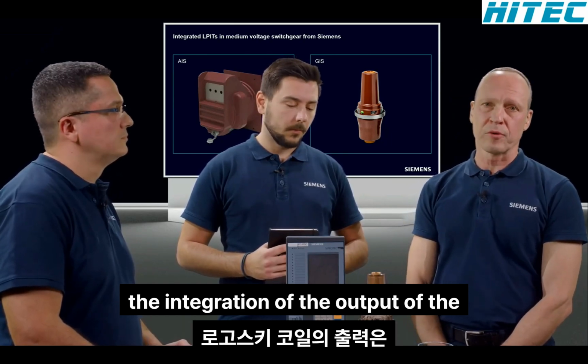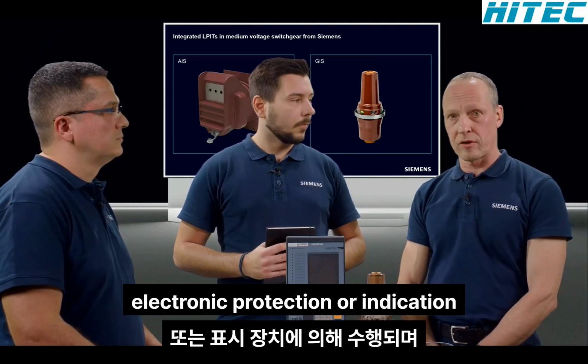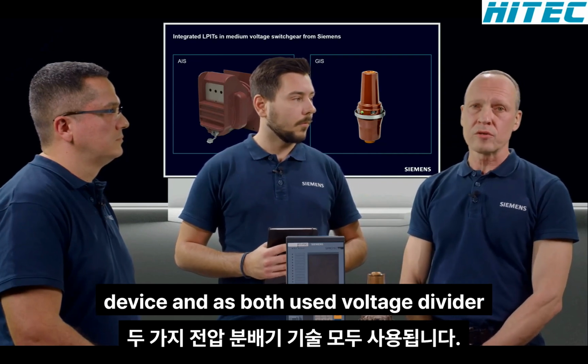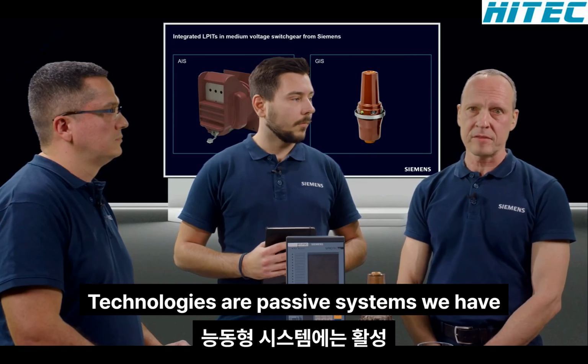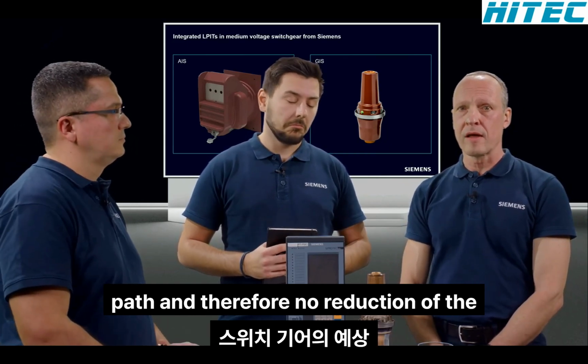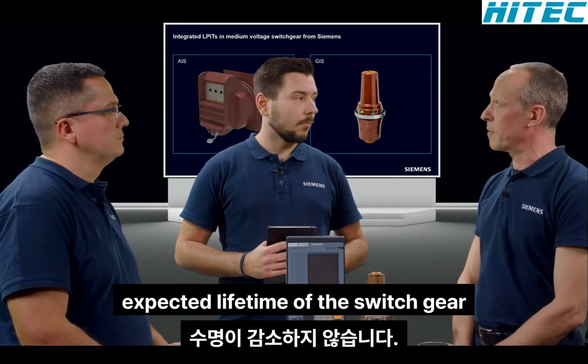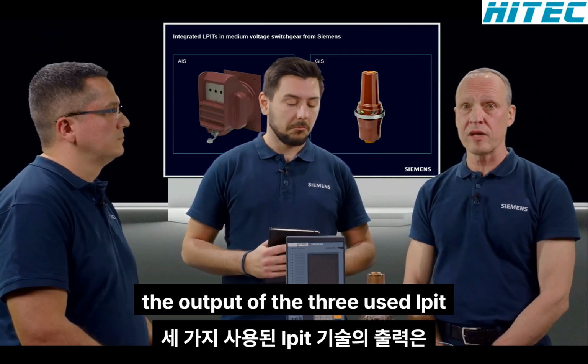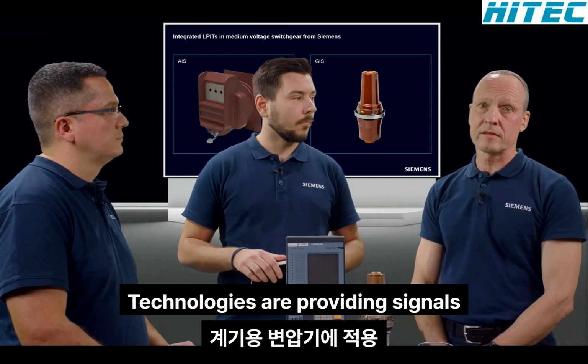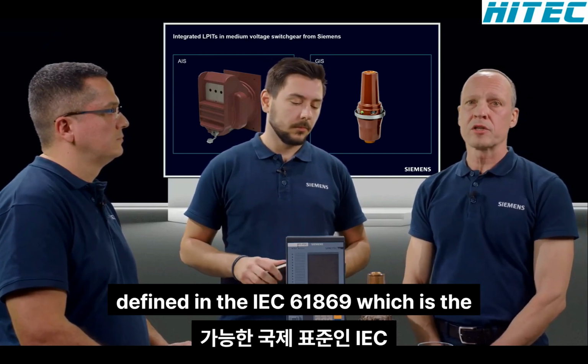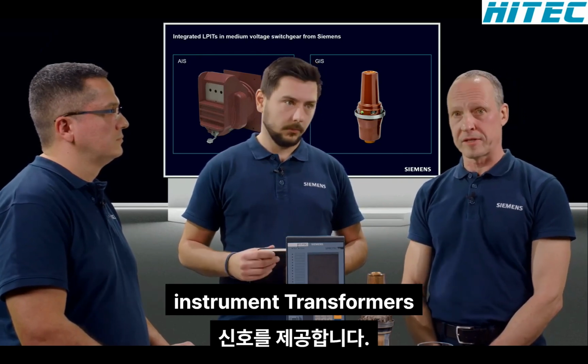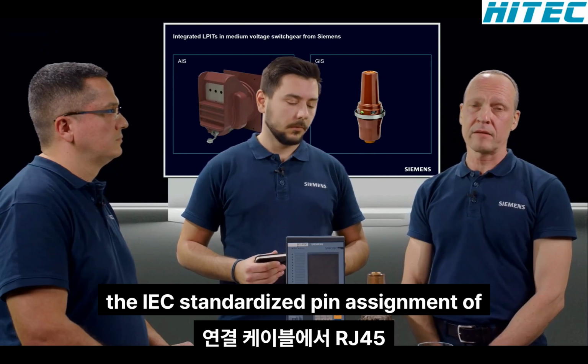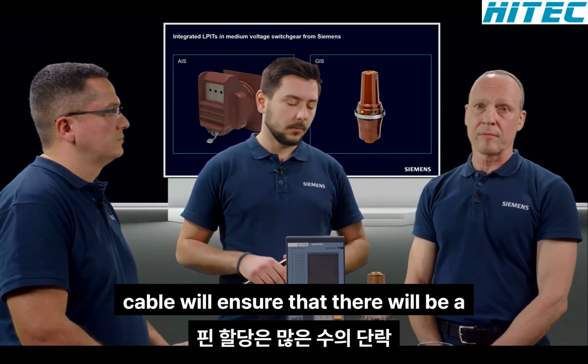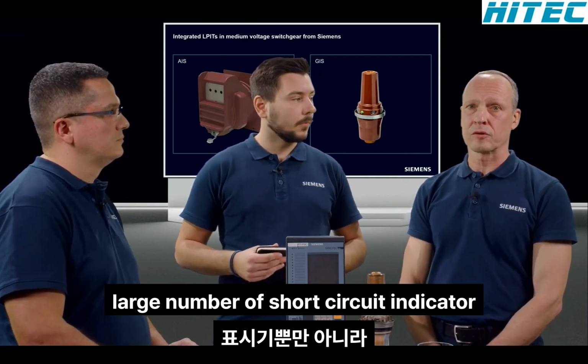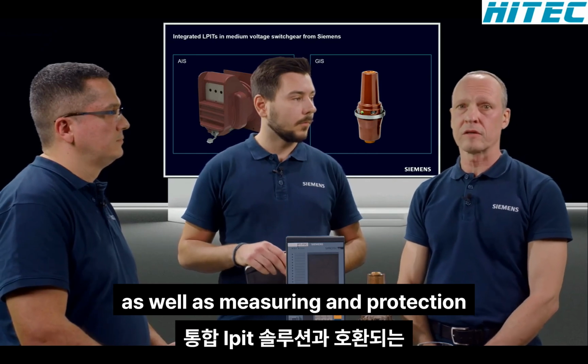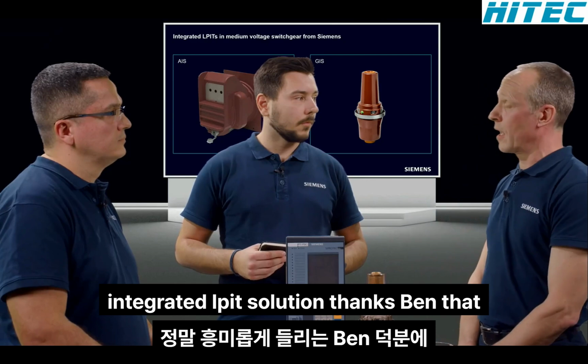As the integration of the output of the Rogowski coil is done by the connected electronic protection or indication device, and as both used voltage divider technologies are passive systems, we have no active electronic in the primary path, and therefore no reduction of the expected lifetime of the switchgear itself. The outputs of the three used LPIT technologies are providing signals defined in the IEC 61869, which is the applicable international standard for instrument transformers. The IEC standardized pin assignment of the RJ45 connector at the connection cable will ensure that there will be a large number of short circuit indicator as well as measuring and protection devices being compatible with our integrated LPIT solution.